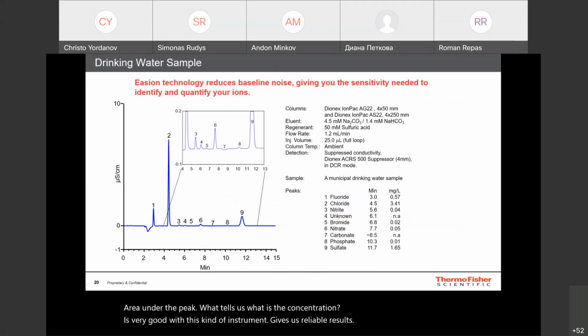On this slide, we can see a real life sample, not only standards. This is a drinking water sample analysis for the same 7 inorganic anions. The concentration of some of the components is less than 1 ppm, like fluoride, nice peak number 1, but also nitrite peak number 3, bromide peak number 5, or nitrate peak number 6. These are even less than 0.1 ppm. If we zoom it in, let's say from minute 4 to minute 13, then we can see these small peaks can be quantified.